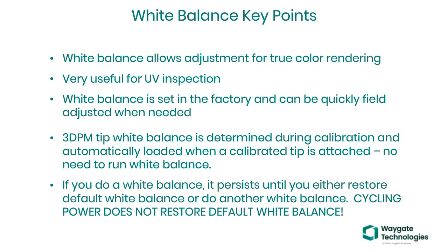And also, remember, when using real 3D phase measurement, the system already recognizes the tip and a saved white balance is loaded, so additional white balancing is not required for that tip optic. A white balance will persist even after a reboot. So to change that, either go to Settings and restore default white balance, or simply white balance manually if needed.